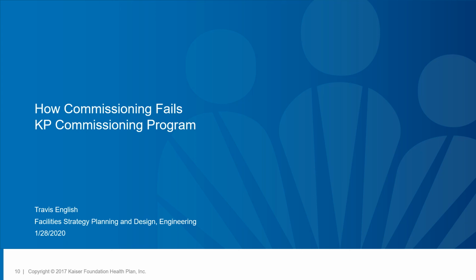But at the end of all of that, we got zones that are out of control. We got VAV zones that don't appear to be working according to a VAV sequence. The VAV air handlers don't appear to be working to a VAV sequence. The economizers don't appear to be working. The heating hot water pumps certainly don't care if it's 65 or 35 degrees outside. So this building is not going to match the design energy model. It's not even going to come close. It's not doing anything that the design energy model had intended.